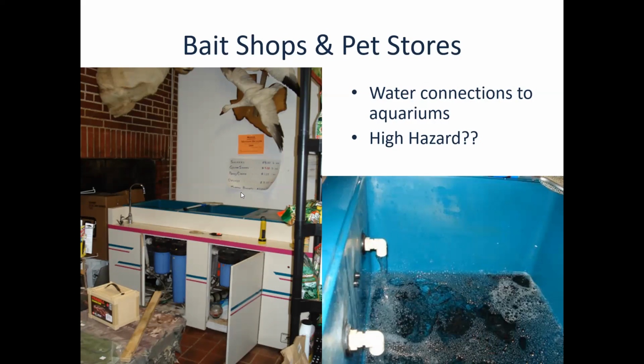Now, if anyone has a guess at what the issue is here. It's that we've got these, again, spigots where we're filling up these sinks, and these tanks are down below the flood rim. So these are definitely going to get submerged. And the issue with the setup is it was claimed to be installed with an anti-siphon device. The problem is that this anti-siphon device is located down below the flood rim. So this is basically an improper installation.